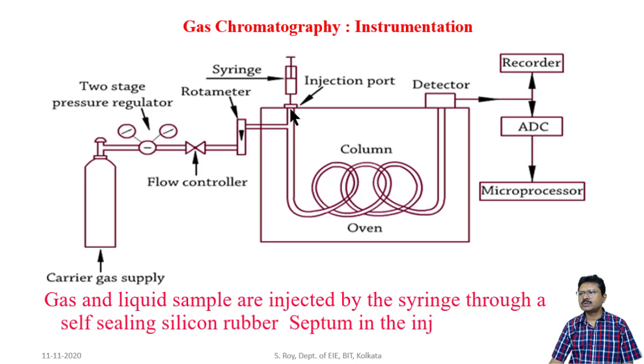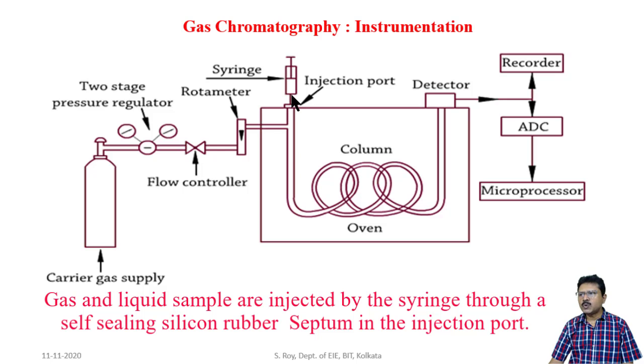Gas and liquid samples are injected by a syringe through a self-sealing silicon rubber septum in the injection port. The sample is inserted here using a syringe; when the needle is inserted into the septum the gas to be analyzed enters into the column, and when the needle is pulled out the septum is auto-refilled — meaning no porosity in the septum remains.